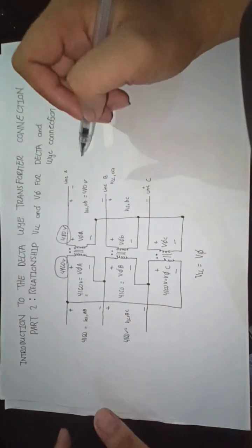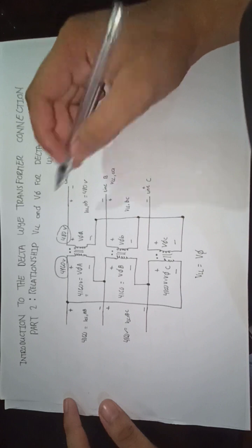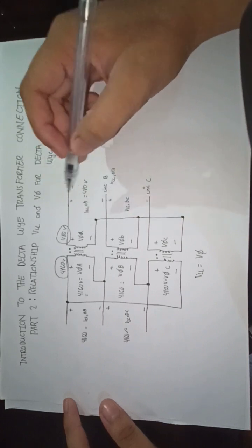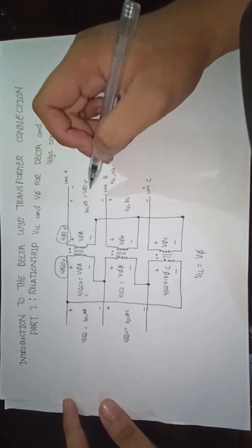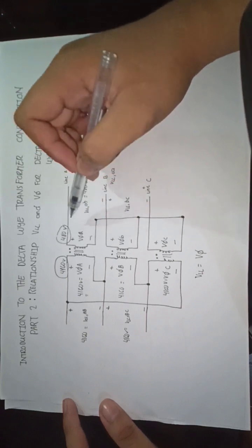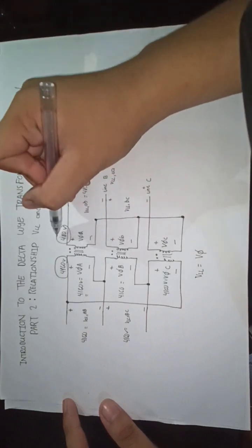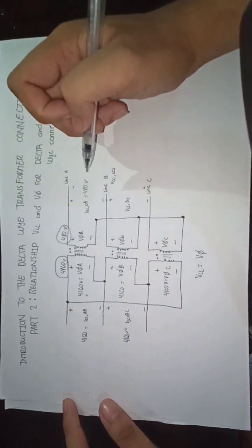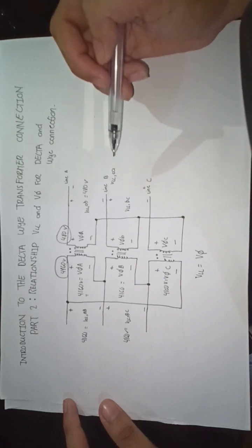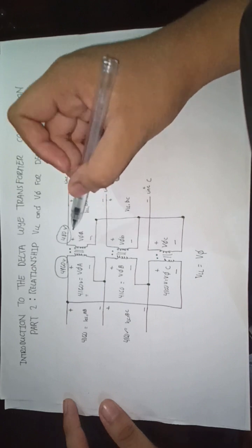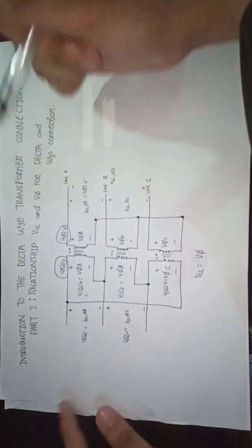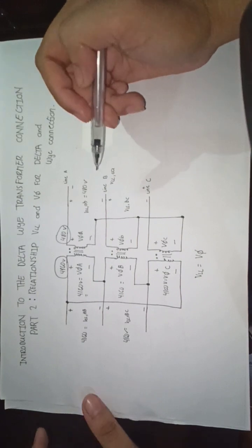While on the secondary side, where our transformer is connected in Y, if we measure the voltage across line A and line B, we should expect 480 volts line-to-line voltage. Again, this is the voltage we assumed in part 1. And so what voltage should we expect if we measured across the polarity side of winding A? Well, we have to derive that from the line-to-line voltage.